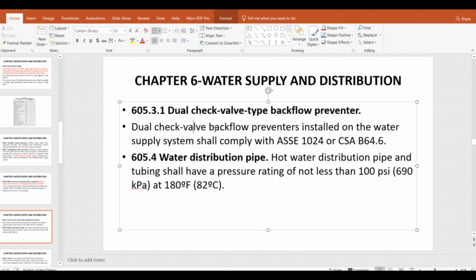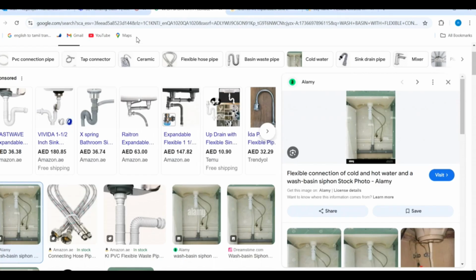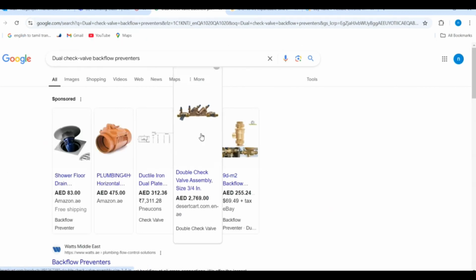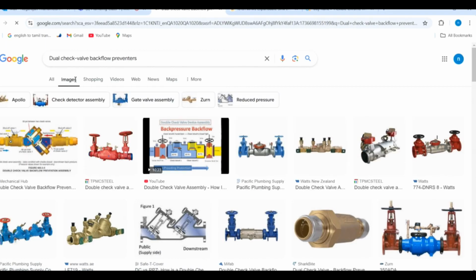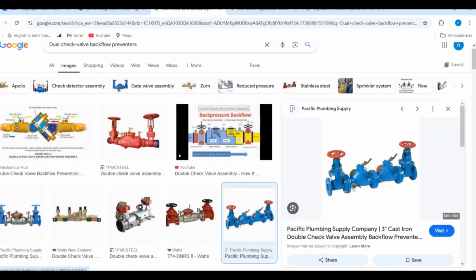What is that dual check valve backflow preventer? Has anyone seen a dual check valve backflow preventer? For the supply line, before the tank, we normally provide it as per IPC. Yeah, like this. Dual check valve assembly means there should be two isolation valves and two check valves. That is called a dual check valve backflow preventer assembly. If at least one check valve fails, the other check valve can still prevent backflow of water. So there should be two isolation valves, two check valves.